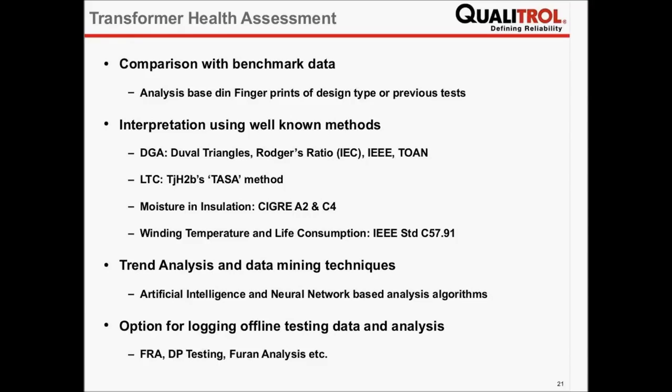So if utilities want to do offline testing like frequency response analysis, PD analysis, furan analysis, then this system should have a facility to enter the results of these tests into the database, and this entered data should be used in all of the future analysis algorithms, all of the future trending, and all of the future models.